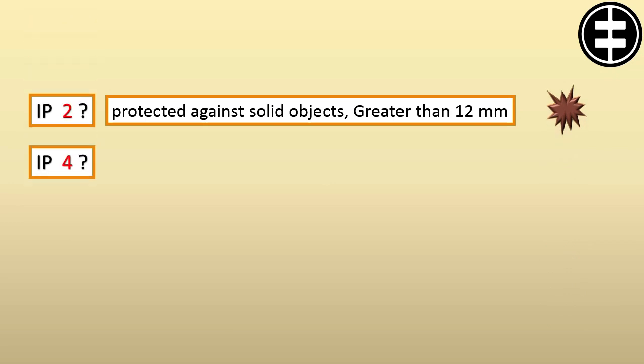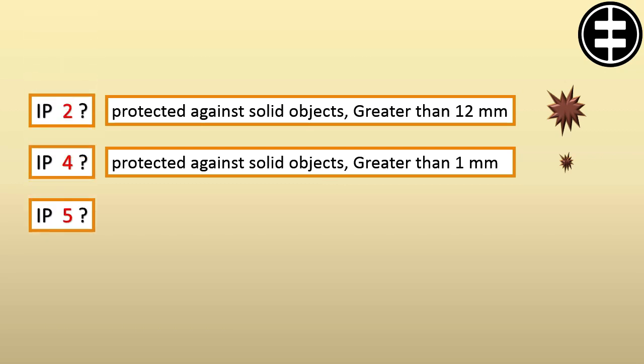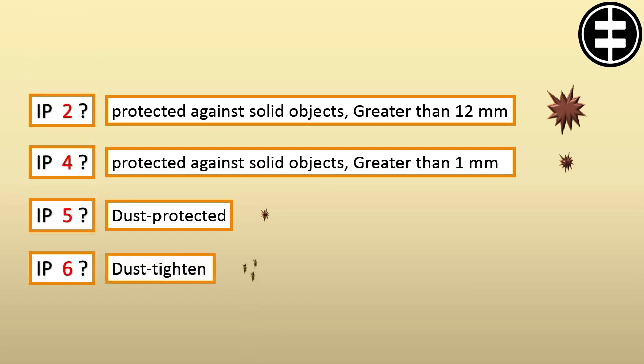If this digit is 4, the motor is protected against solid objects greater than 1 millimeter. If this digit is 5, the motor is dust protected. If this digit is 6, the motor is dust tight.